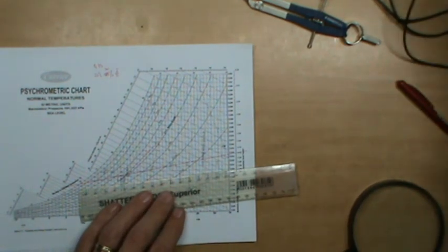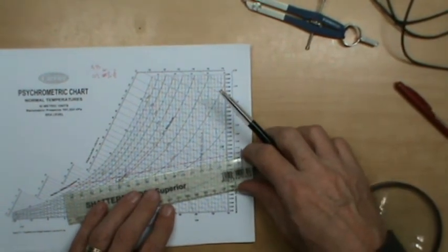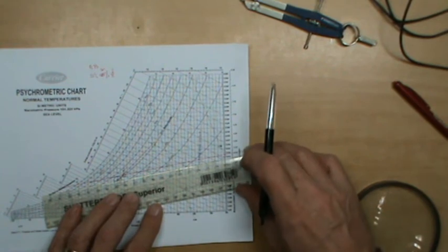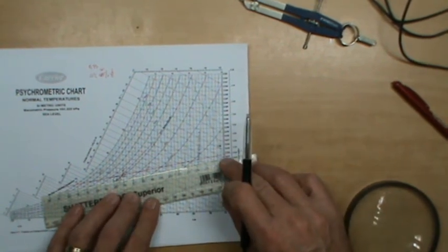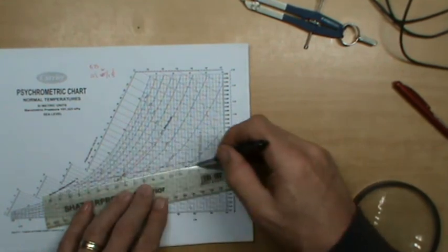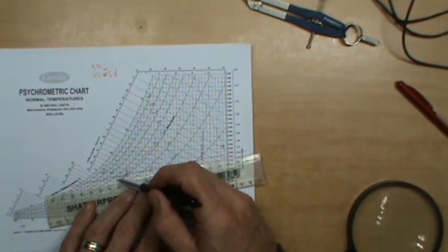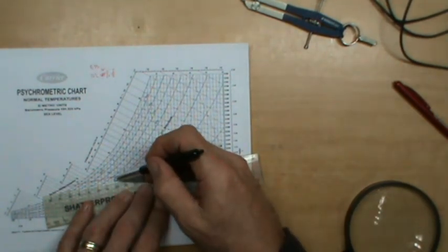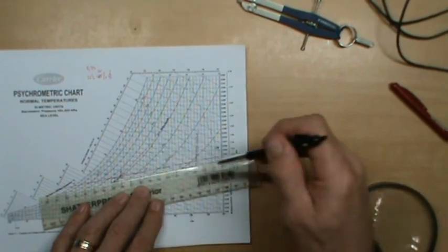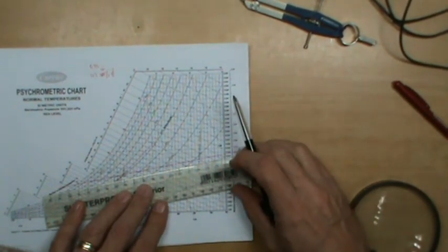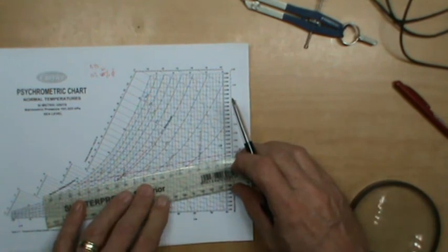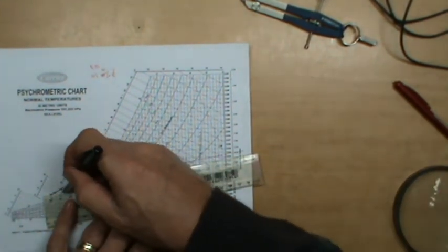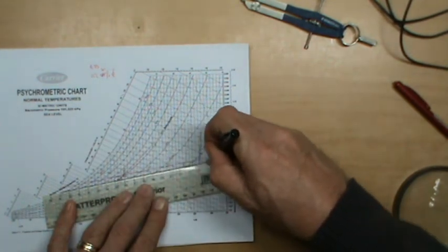And I then join up, and I'll draw this one in black, from that second point, state point 2, to that arc. So in other words, what I've essentially done is I've ensured a parallel line by having, I know what that distance is, and by doing another arc over there, which is the same distance from that red line as what that state point is, I can ensure that line is going to be running as close to parallel to that effective room sensible heat factor line as possible. And there I go and draw it.